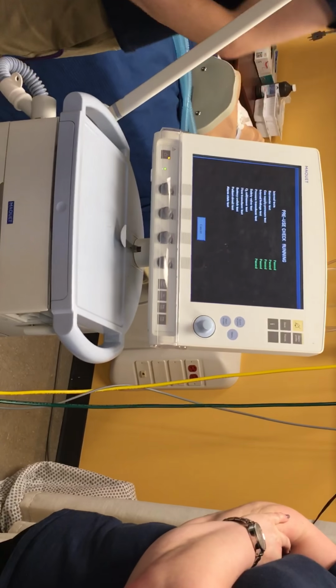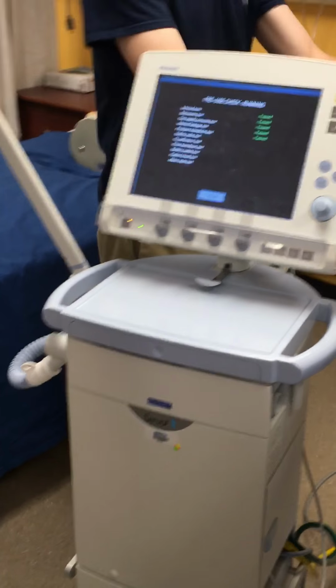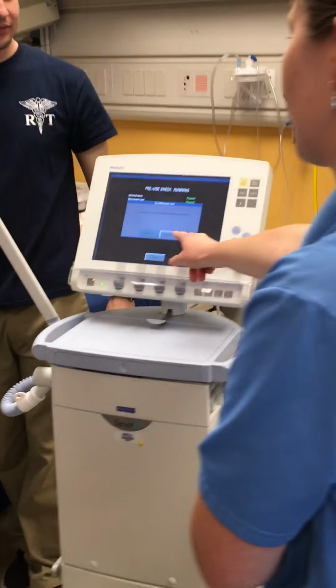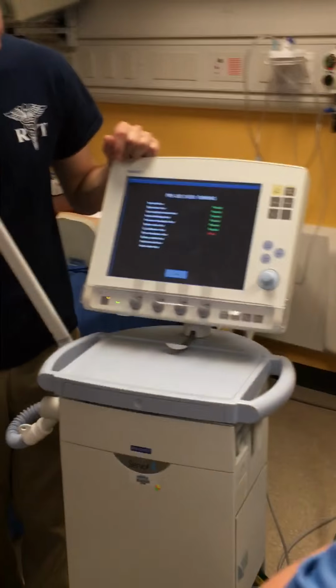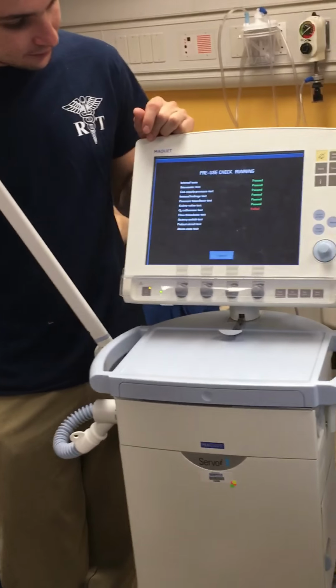Is it still calibrating the O2 sensor? No, it's not. That's been a challenging group over there, especially with the tubing plugged into the exhalation valve. Just push cancel for this, right? Since we don't have it. Yes. It's going to say it failed, we know it.